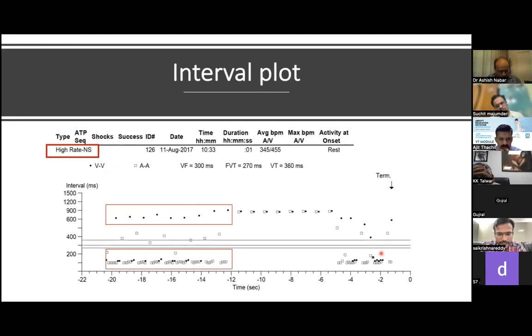So these are the intracardiacs. The top channel displayed is RV coil to can, which is far field. The second one is RV tip to ring, which is near field. And the third one is the marker channel. What is being seen here is a very high frequency, non-physiological, almost instantaneous signal in both the channels. But what is the device seeing? It is actually seeing only the signals in the atrial channel, not the ventricular channel. You can see there's undersensing of these non-physiological external signals.